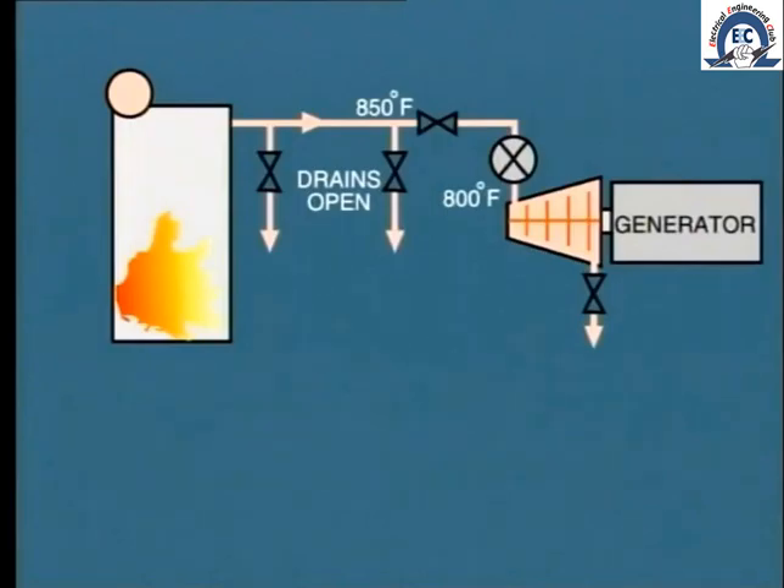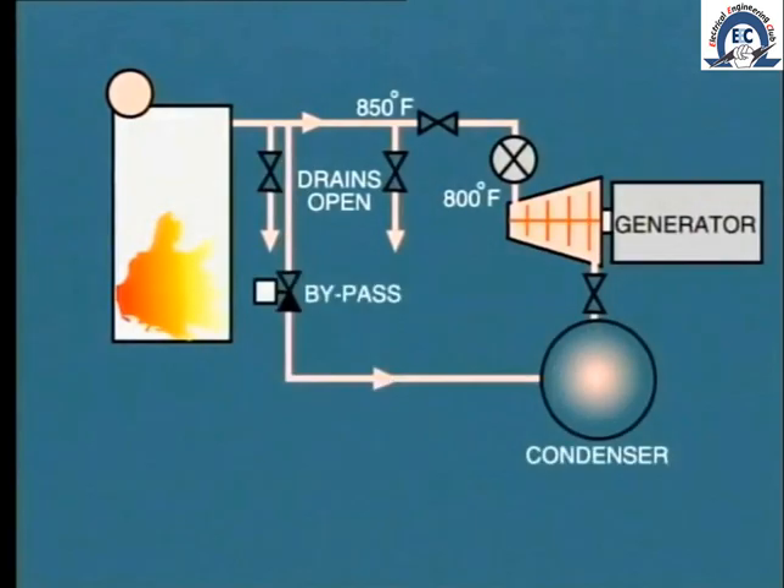In units which are installed specifically for two-shift operation, a steam bypass arrangement may be built into the system to permit this increase in steam flow during startup. As we see from this schematic, the bypass system allows an increase in steam flow through the boiler by bypassing the turbine. The excess steam is dumped into the condenser where it is cooled by the circulating water. Of course, there is a heat loss involved, but we do achieve the objective of providing a hot start and improving the life of the turbine.